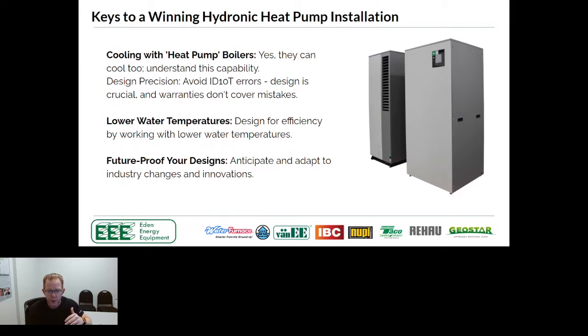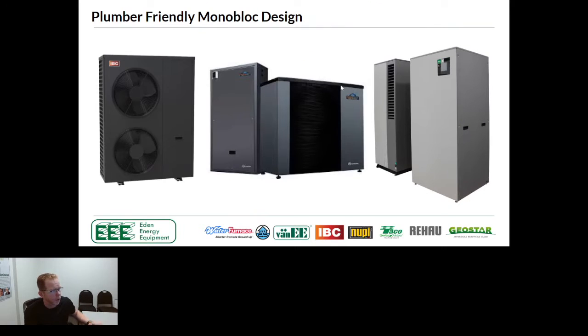So you don't want to be doing any sort of rules of thumb is where I'm going with this. Make sure that if you're doing your first hydronic heat pump installation, you have some talented people around you. So that can be either the manufacturer, that can be a great distributor, but make sure that you're future-proofing your design. And what I mean by that is design for the principles right now. Don't design for what you've been taught in the past, because although that's all great knowledge to have, it may not transition one-to-one from what you would do with a boiler as to what you would do with a hydronic heat pump.